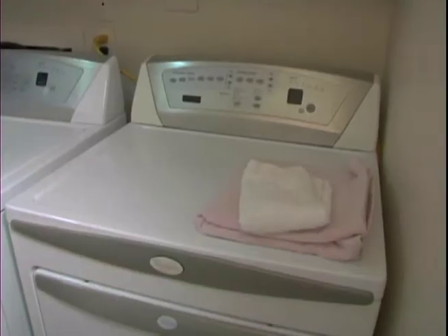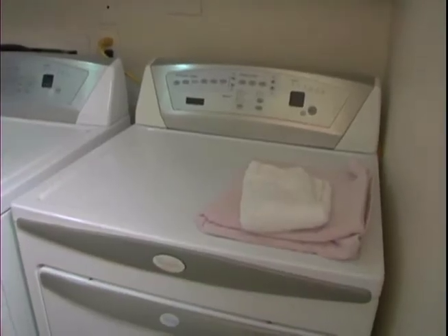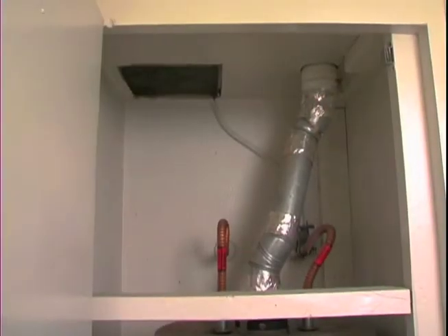The clothes dryer in this room moves 200 CFM of air out of this room. We want to make sure that it's not getting it out of this closet. Okay. Since we can't see air, what we're going to do is with the smoke pencil, we're going to put smoke into the air so we can actually see where the air is traveling. Okay, can we do that now? We can. Charlie, can you get me a smoke pencil? Sure I can. Here you go.